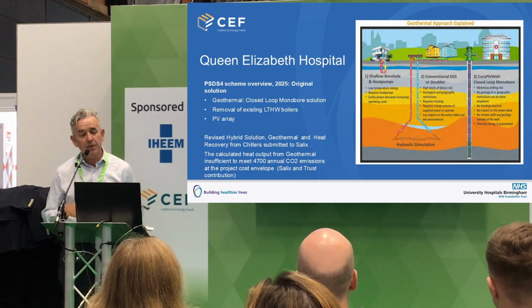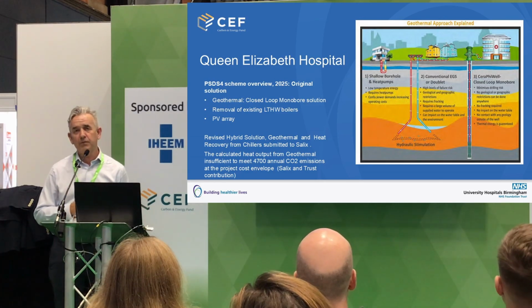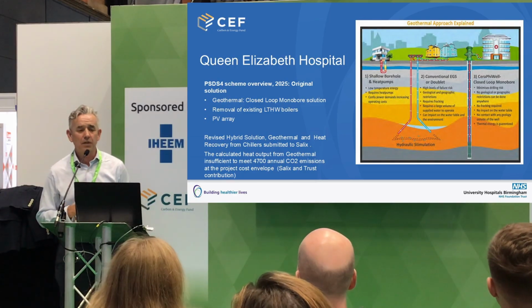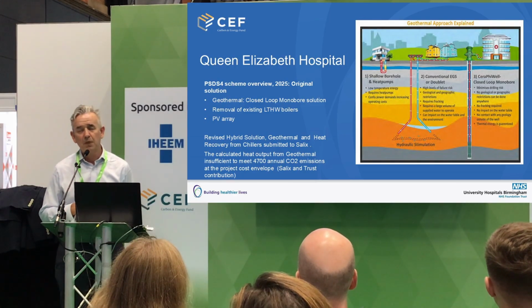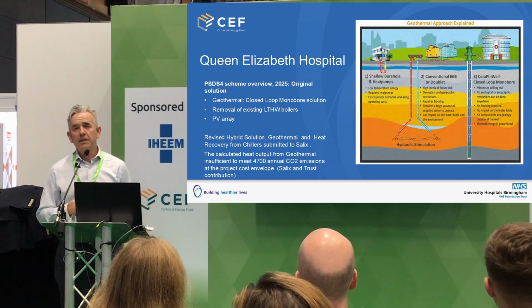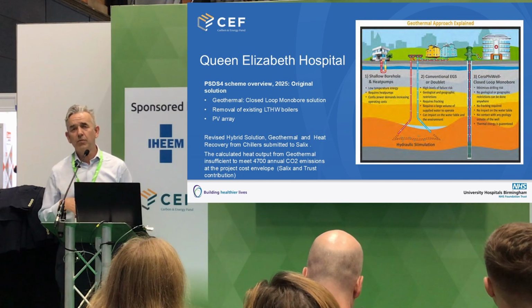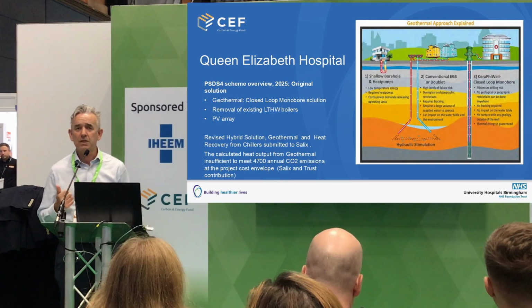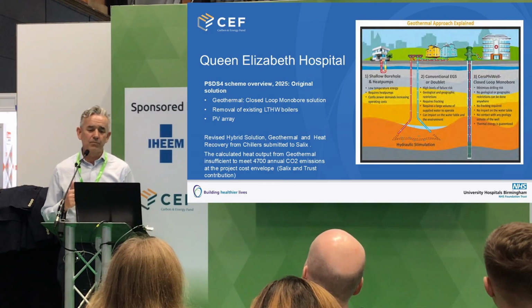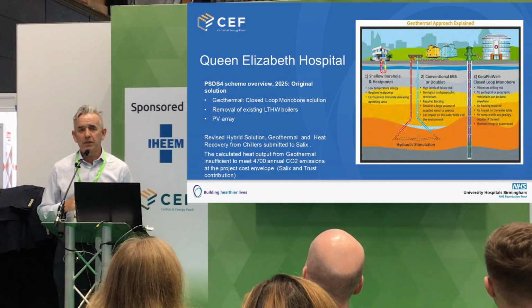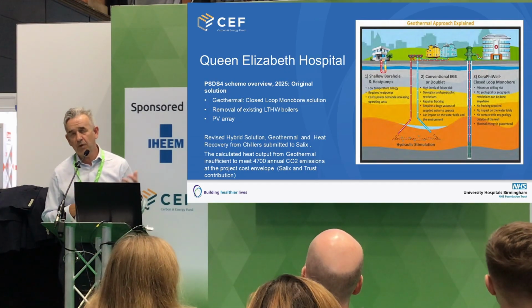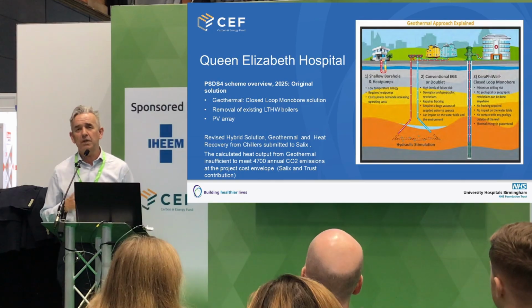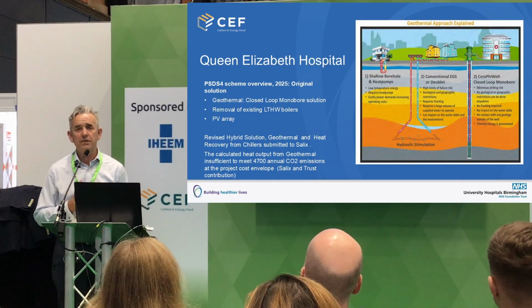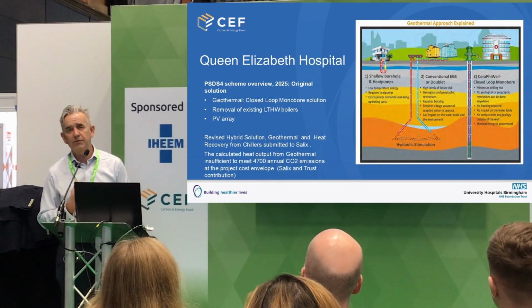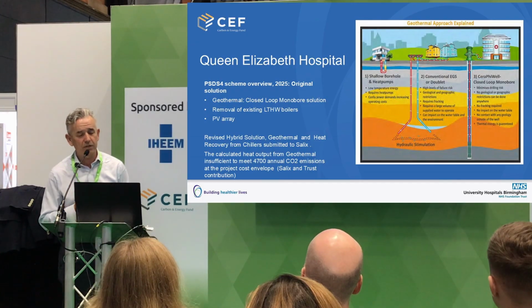Finally, on the PSDS4 schemes, we were successful on a geothermal solution at the QE hospital. We decided, because of some of the data, to do a further feasibility study before going full gung-ho into the process. What we found on that second, more detailed feasibility was that we just weren't getting the heat output we originally thought we would — either lots of low-grade heat at temperatures between 5 and 10 degrees, or a limited amount of water coming out at 25 to 30 degrees.